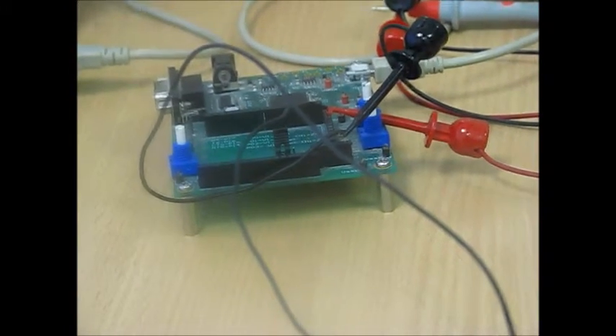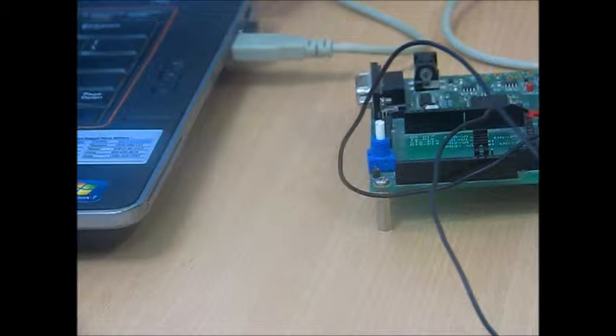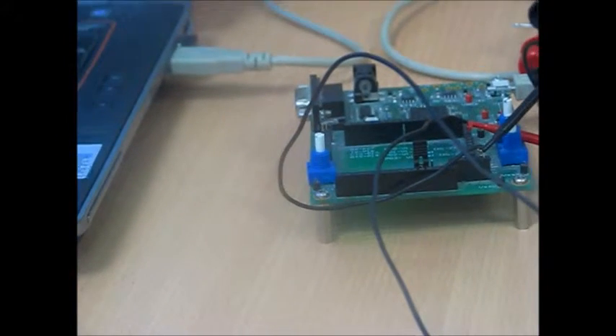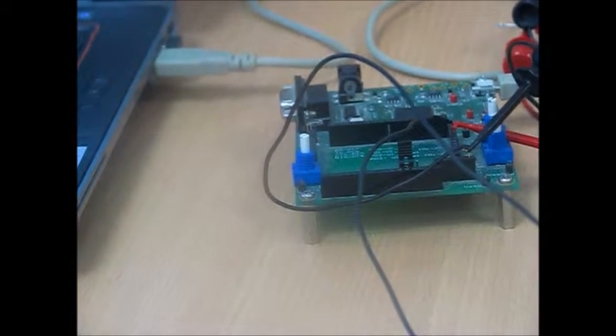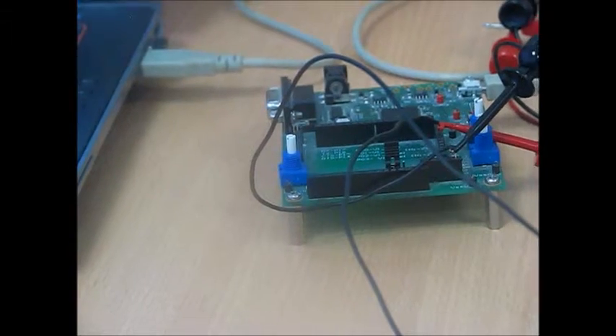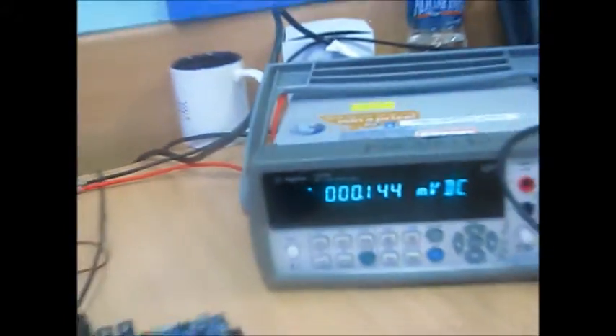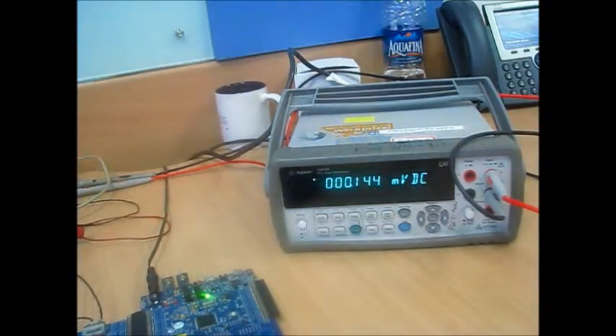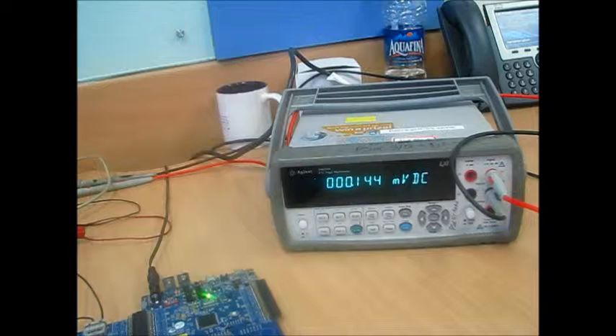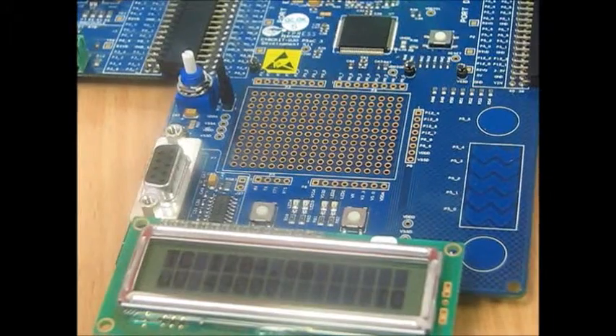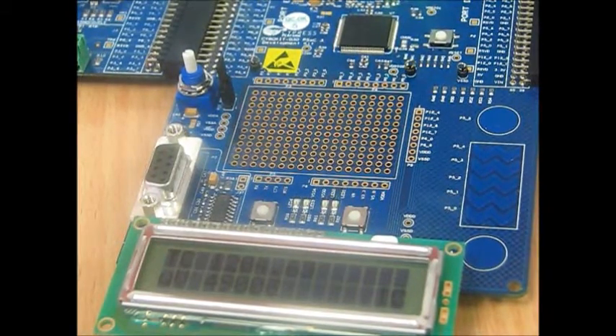It's powered by the USB of the laptop so that the grounds of the two systems remain separated out, as required for a thermocouple system. And I have a 6.5 digit multimeter that's 0.025% accurate as my absolute reference source against which I'll be benchmarking my measurements. After programming the device, let's press reset.